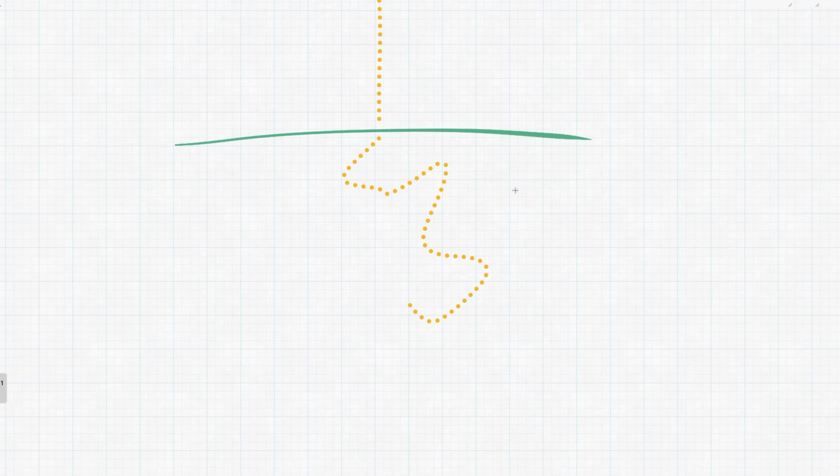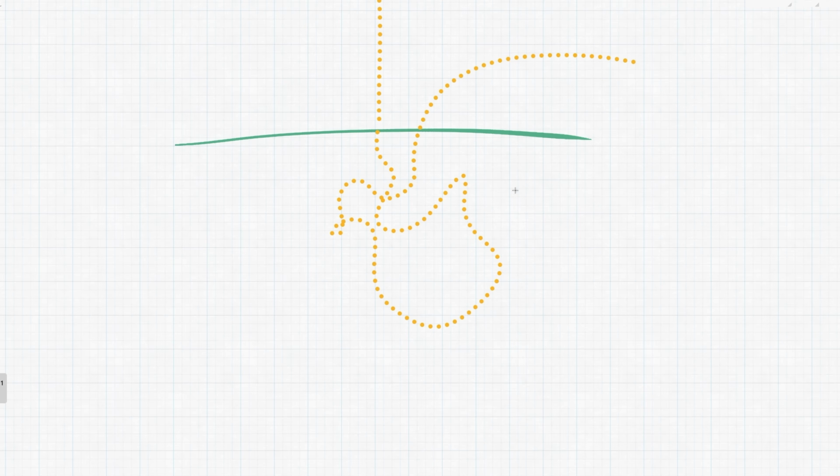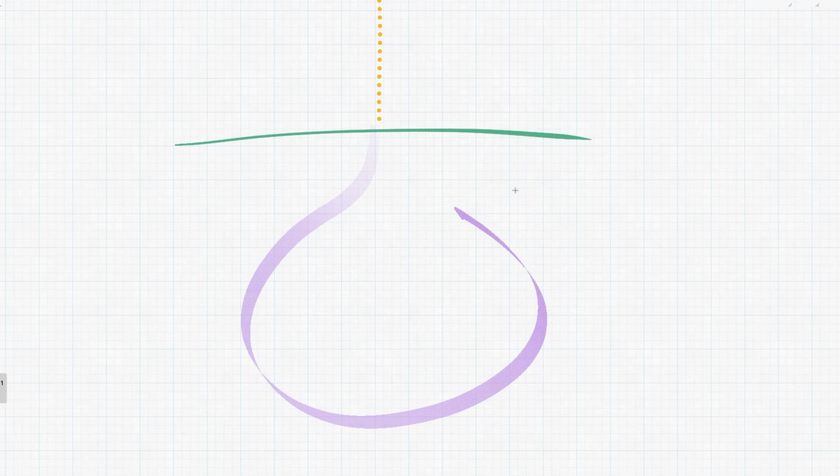We make this distinction because an electron has a certain interaction volume inside of a sample. So if we have a bulk sample here, when we hit it with an electron beam, that electron can kind of bounce around inside the sample before it does something and is emitted as a backscattered electron, or it'll bounce around and then be emitted as a secondary electron. And this area where it bounces around is known as the interaction volume. And it tends to be shown as a kind of teardrop diagram, where statistically, this is where an electron will interact with something before causing an event.